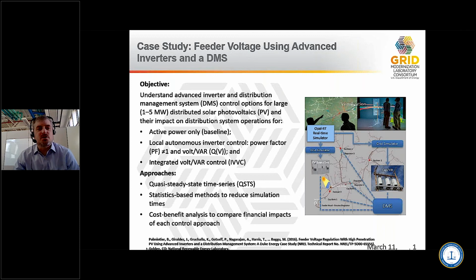In this case, we're looking at a large 5 megawatt distributed PV system. This is very typical of a North Carolina type area, the way they're seeing PV being rolled out currently, connected to distribution. We see this a lot in California as well. The question is, with that 5 megawatt PV system ramping up and down a lot, it has a large impact on the voltage regulation equipment on the system, as well as the customers. How do we try to mitigate that as best as possible?